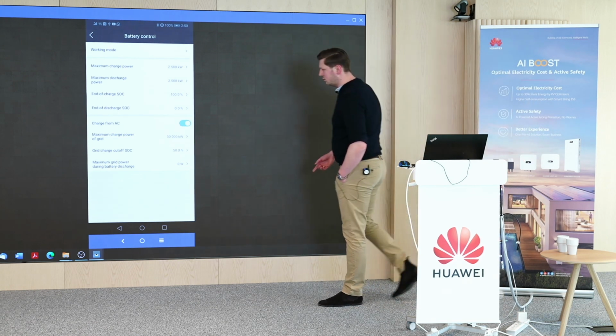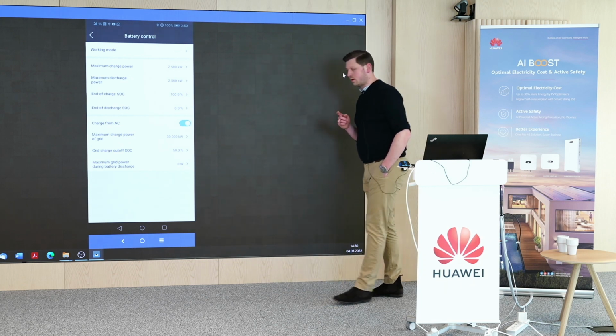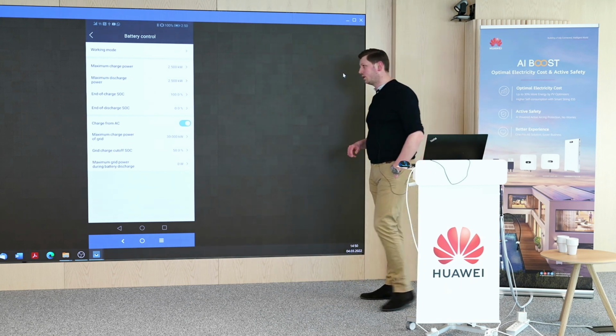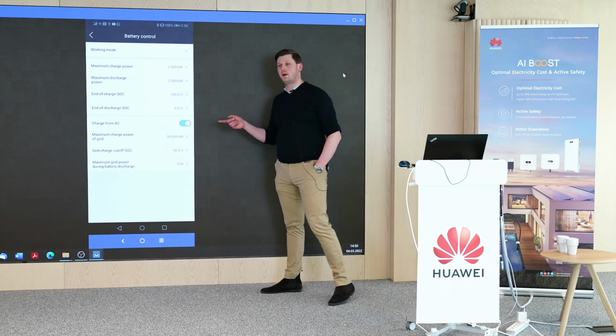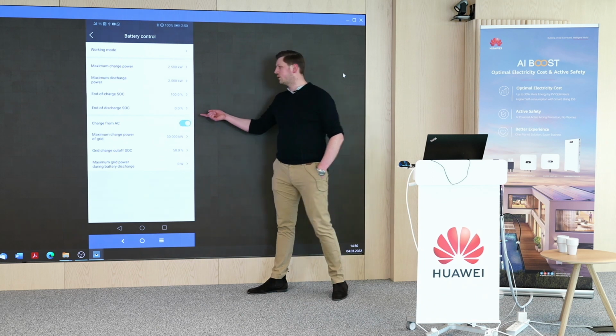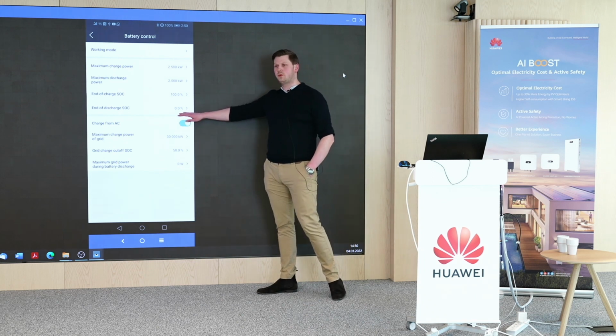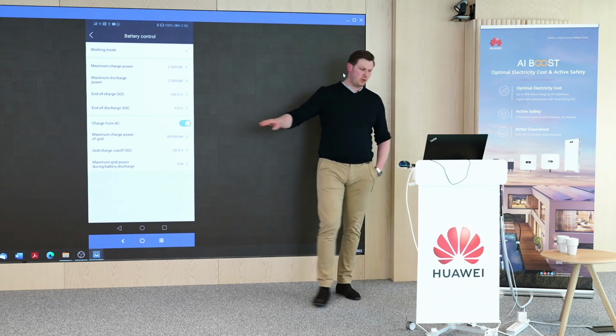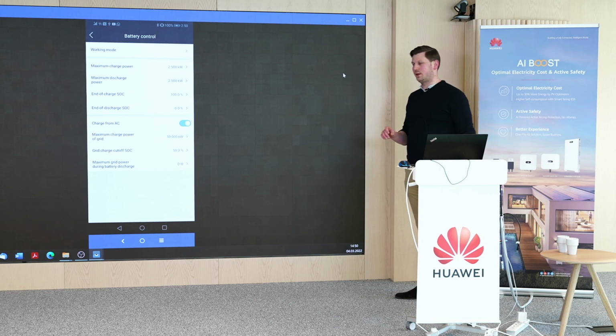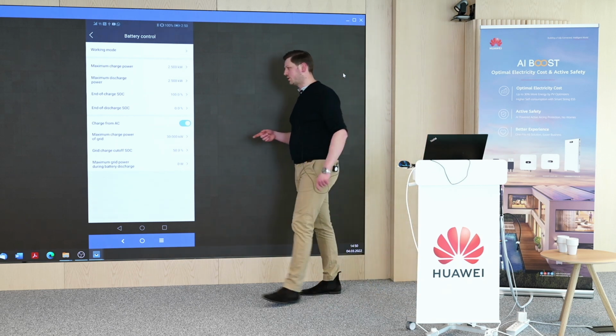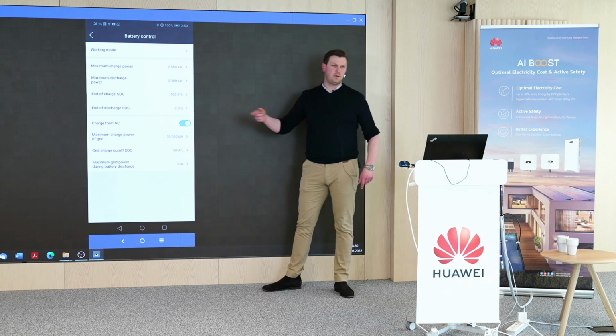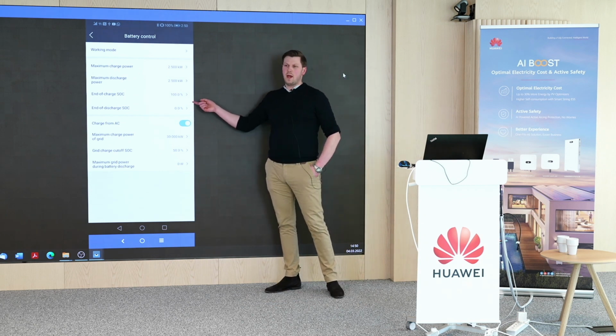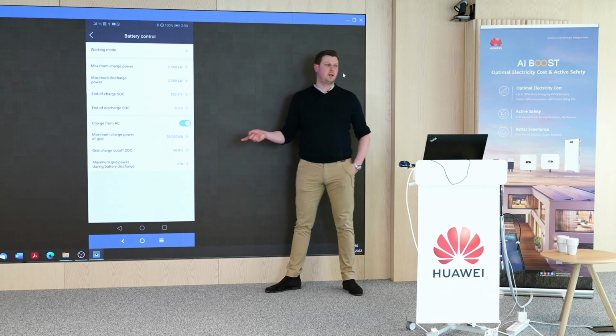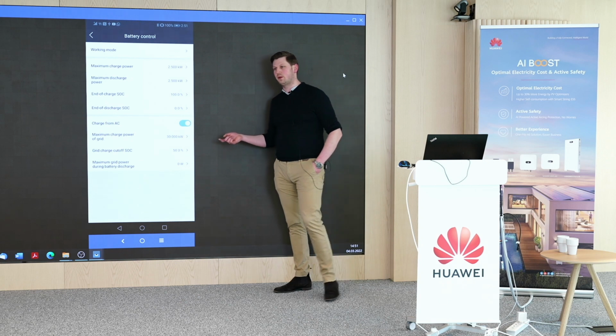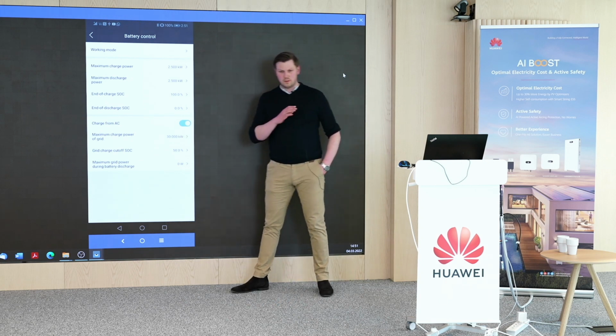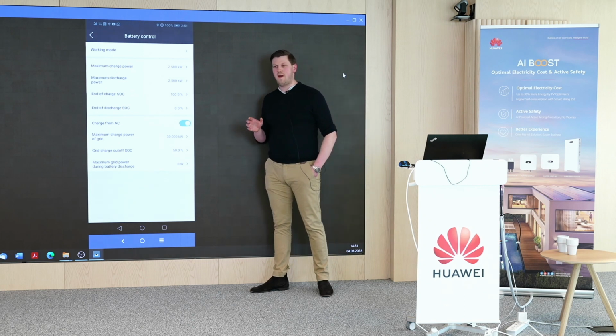You can control all these parameters from this local app as well. You can choose the maximum charge, discharge power, end of charge SOC, end of discharge SOC. Don't worry to put 0 here, because the Luna battery has more capacity than the declared 5 kilowatt hours, so 0 doesn't mean the battery is fully empty. Of course, I wouldn't recommend using it like this if it's mounted outside the building, because during winter time it might discharge itself and affect the state of health.